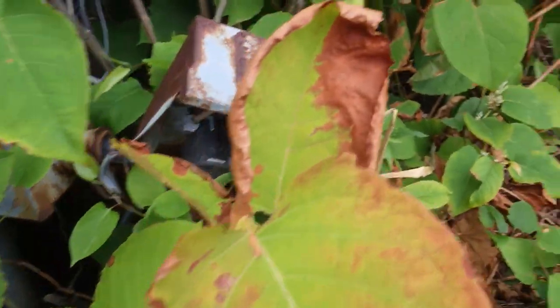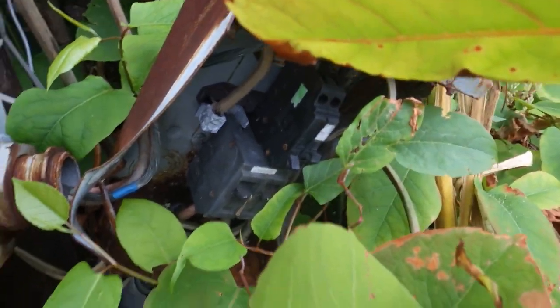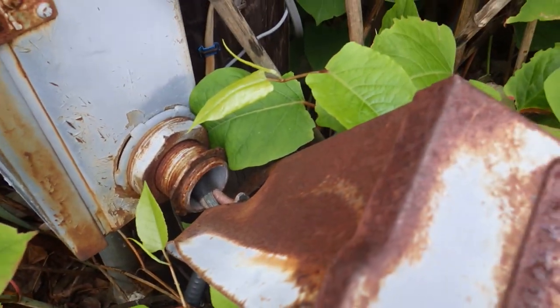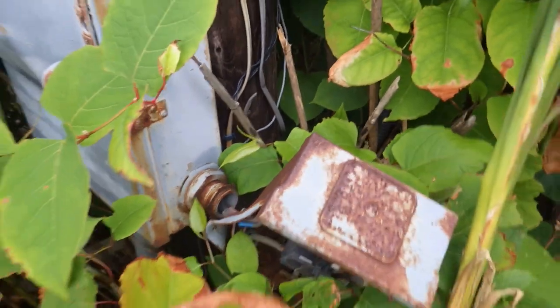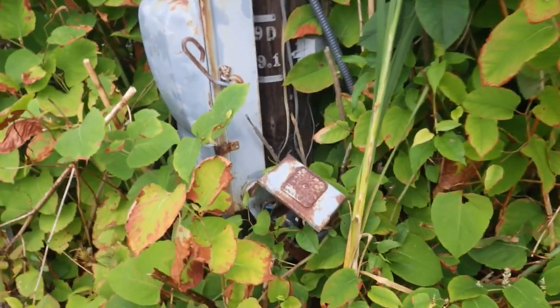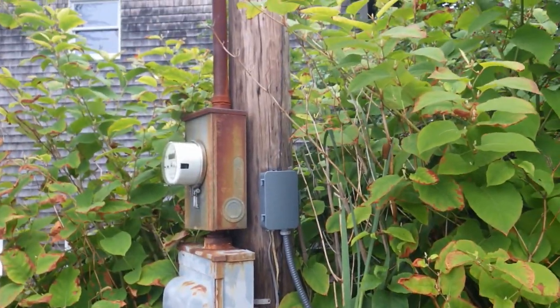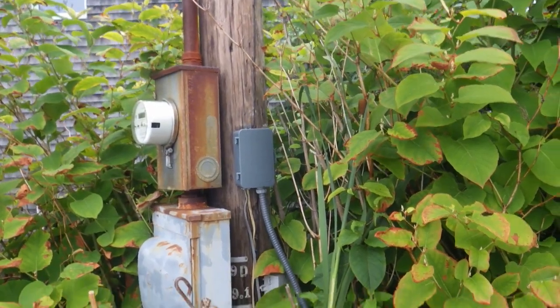Hello everyone, this is Russell Blank, your NEC consultant for EC&M magazine. I spotted this mess at the edge of a parking lot after I parked my car. Look at that — broken raceway, exposed conductors, panel board missing its cover.